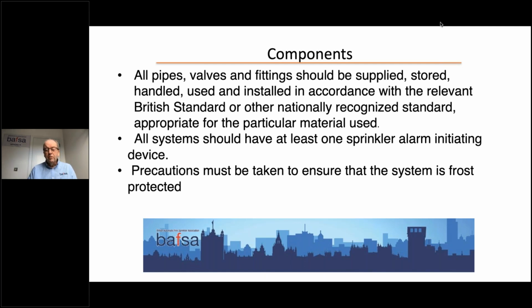In most cases, the frost protection will be required in the roof space for the pipework that goes in there or for the tanks that go there. The pipework can be laid in the roof space, and then the lagging or the insulation for the roof can be laid on top of it. In some cases, further protection may be needed, particularly in a particularly cold area, and trace heating may be required for the piping. But again, this will be assessed by the designer and the installer and provided when they do that work.